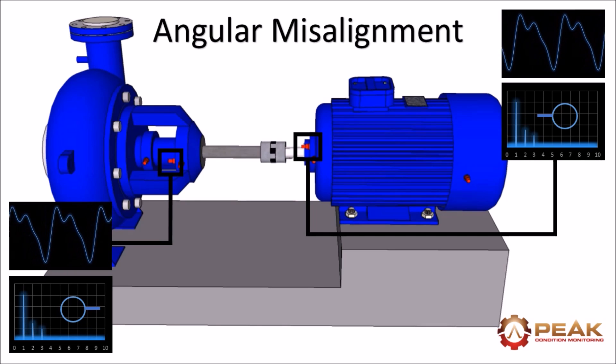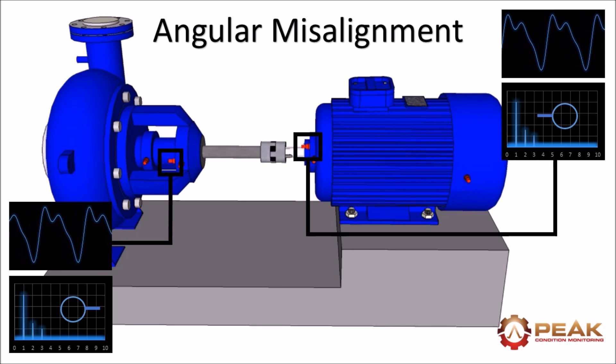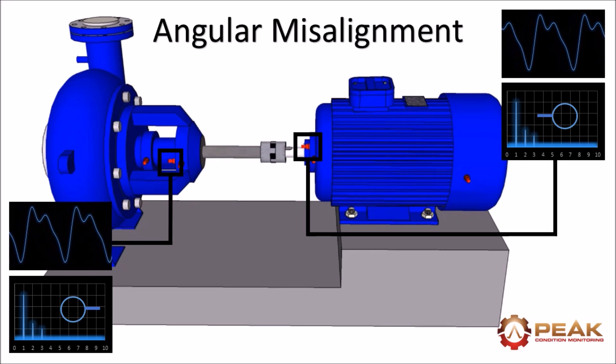If angular misalignment is present you'll again see the 1x, 2x and 3x peaks but in the axial direction and again the waveforms will be out of phase.